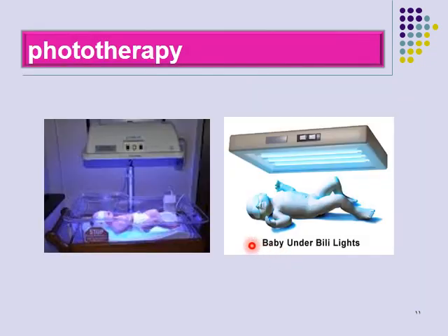These are two types of phototherapy, and this is the light. It is different from the fluorescent light in the home. It is completely different; the light in the home is ineffective. This one has a special wavelength and irradiance.